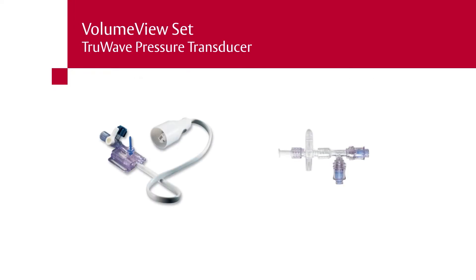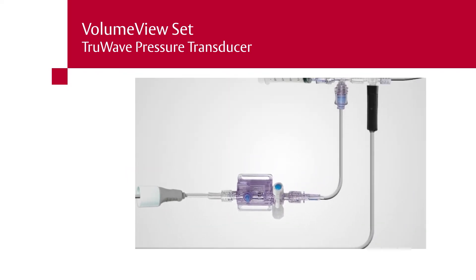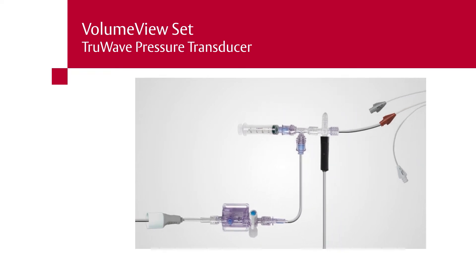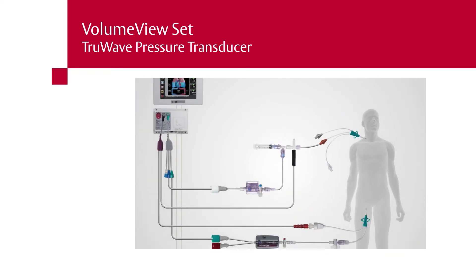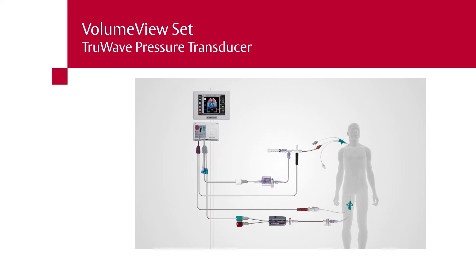TruWave pressure transducer and thermistor manifold. The TruWave pressure transducer is connected in-line with a central venous catheter, or CVC, via the volume view thermistor manifold. These are used to continuously monitor central venous pressure, or CVP, on the bedside monitor and the EV1000 clinical platform. The thermistor manifold allows for the injection of a cold bolus through an injection port, as well as the measurement of the bolus temperature with an inline thermistor.